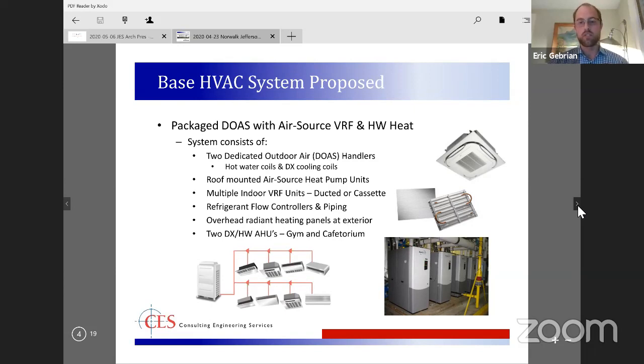And then lastly, hot water heat. We're proposing a natural gas boiler plant for this building. The building currently does not have natural gas to the site, but we're working with Eversource to get it there. It's currently heated entirely by electricity, which is very expensive, and natural gas is a much lower cost fuel to heat with. There'll be a hot water boiler plant supplying hot water for the entire building to perimeter radiation, and it will also provide the heating for the DOAS ventilation system. I'll pause there for any questions before moving on to more detailed HVAC stuff.